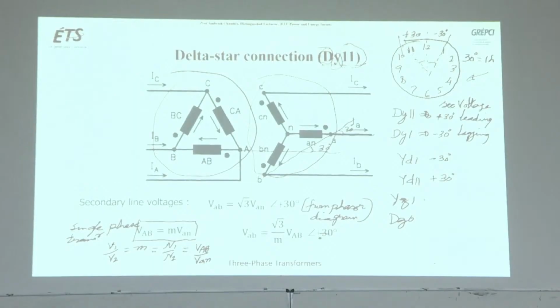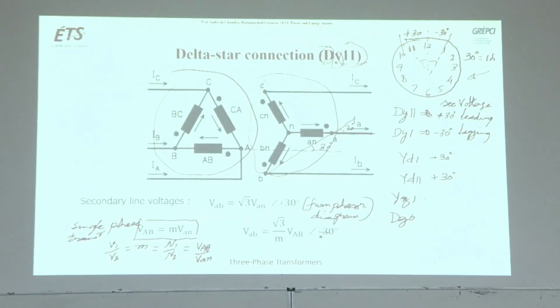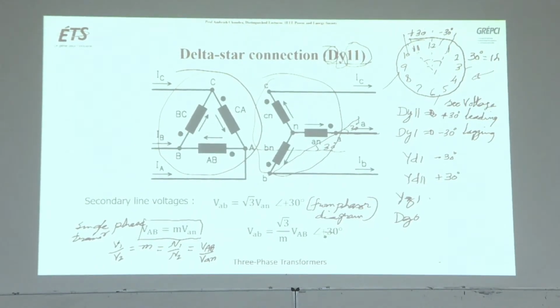So you see this diagram, I have already drawn this diagram, and this is the clock. So 12, 3, 6, 9, those are there, okay? And 360 divided by 12 means every hour represents 30 degrees, right? So 30 degrees represents 1 hour. So if we say 11, this is the reference, and if this is on the primary side, on the secondary side we have 11. It means the secondary side voltage is leading by 30 degrees. So if you use this transformer, on the secondary side it will give 30 degrees leading.